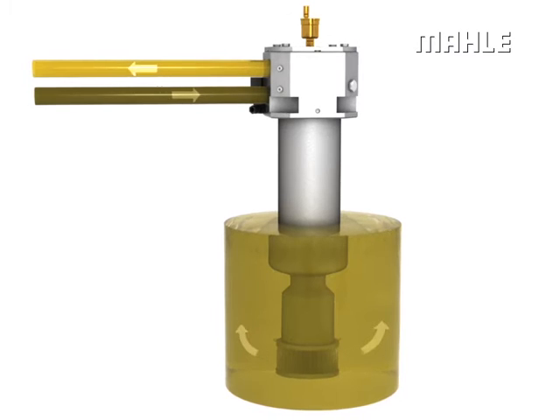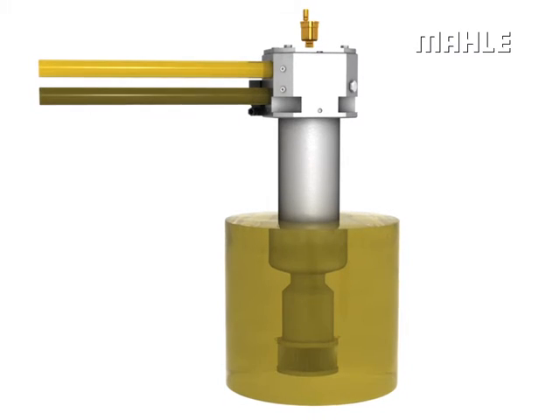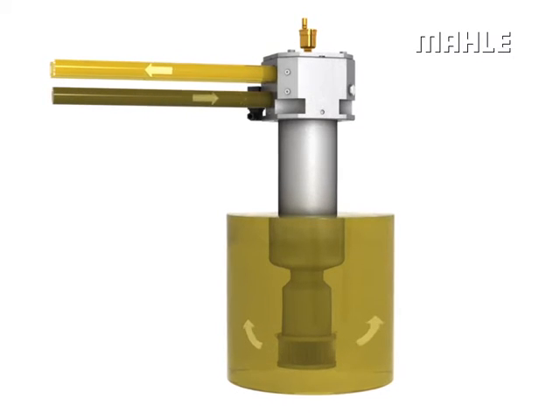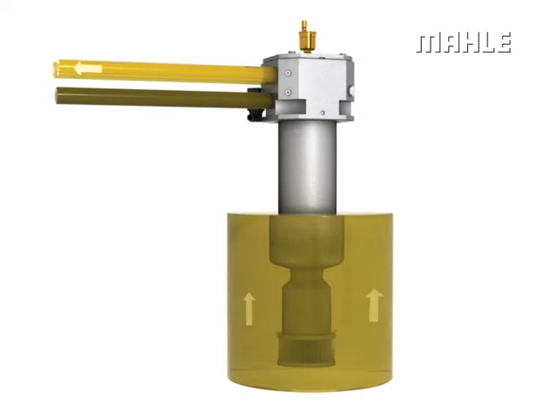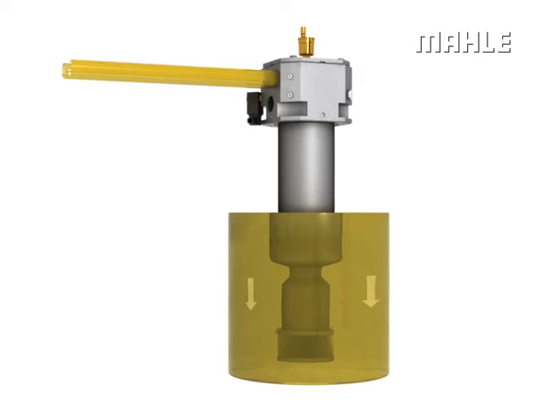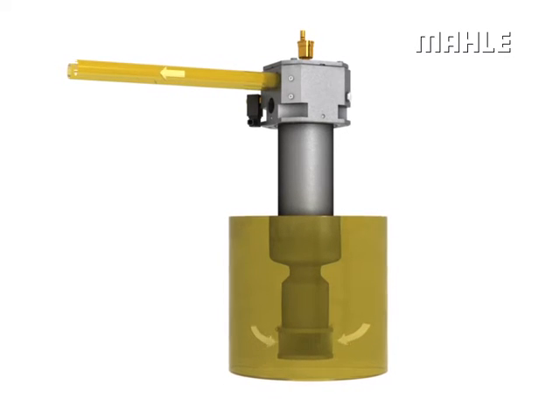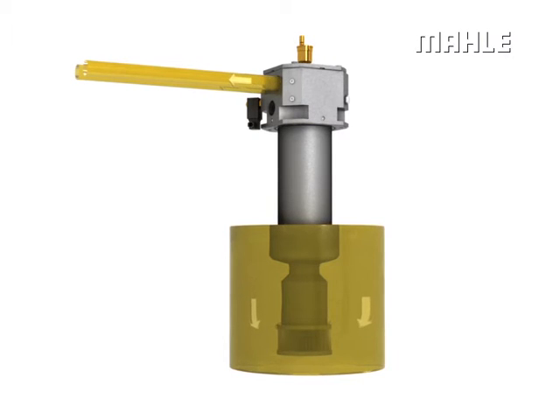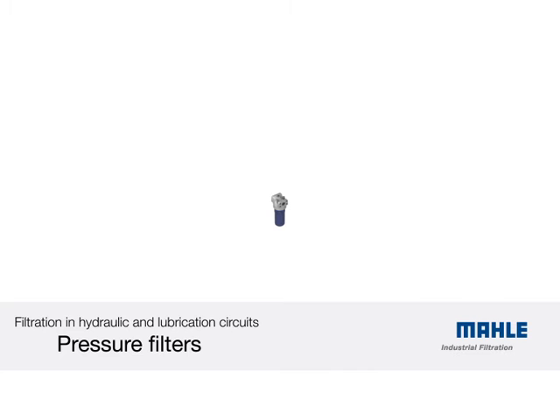As a result, oil that has undergone high-efficiency fine filtration is delivered to the suction pump under positive pressure. In the event the return flow is interrupted briefly, the pump can continue to draw oil directly from the tank through a valve and a coarse protective filter.